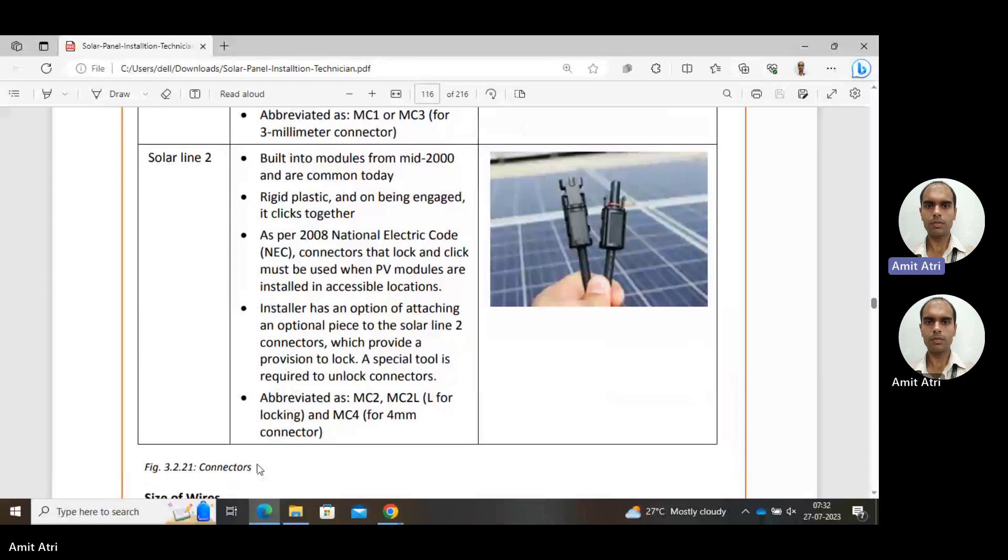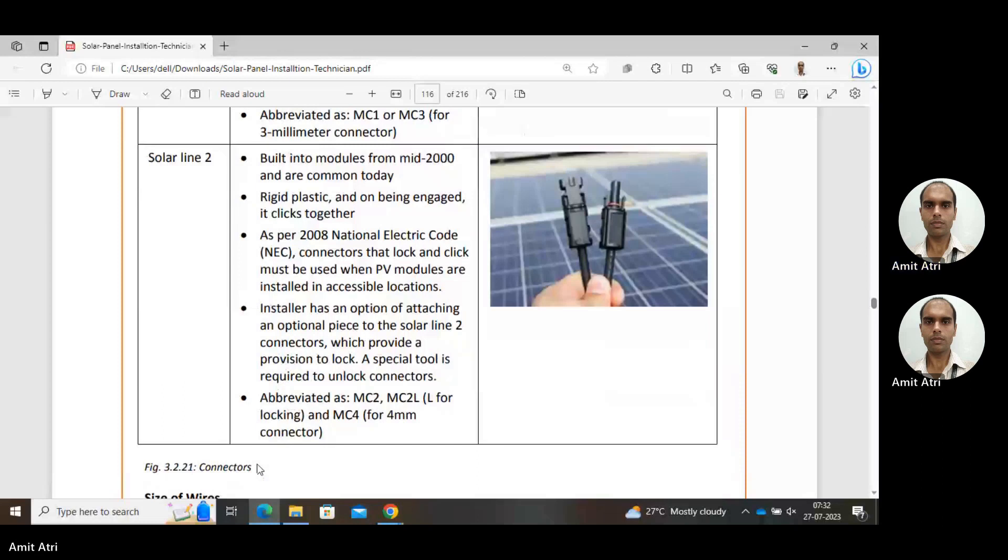Solar Line 2 is built into modules from mid-2000s and commonly used today. Ridged plastic ends engage and click together. As per 2008 National Electric Code, connectors that lock and click must be used when PV modules are installed in accessible locations. The installer has an option of attaching an optional piece of the Solar Line 2 connector which provides provision to lock. A special tool is required to unlock connectors for safety and reliability purposes.